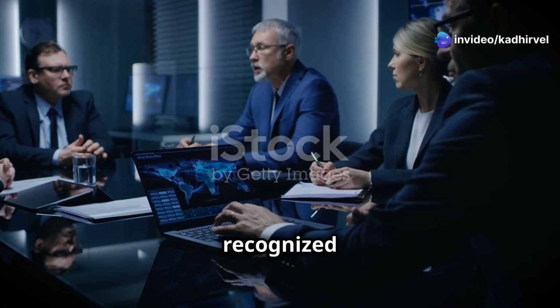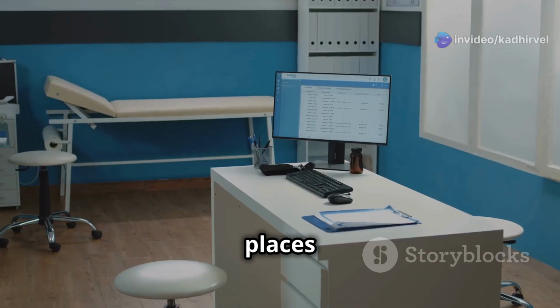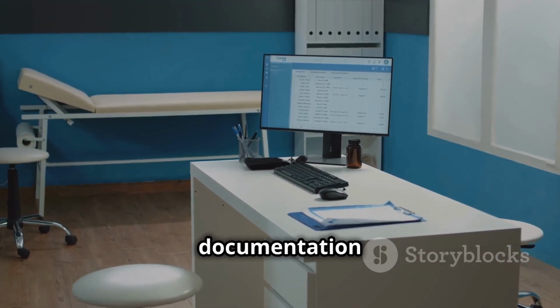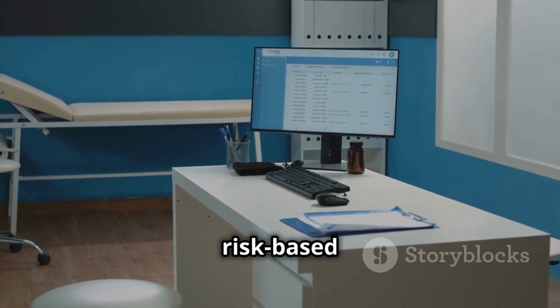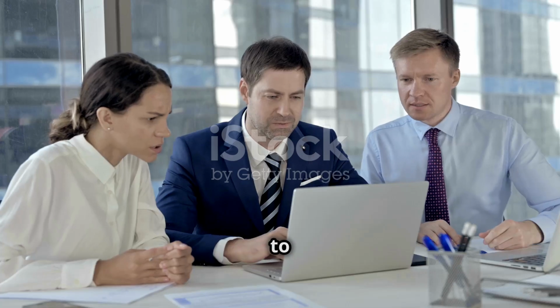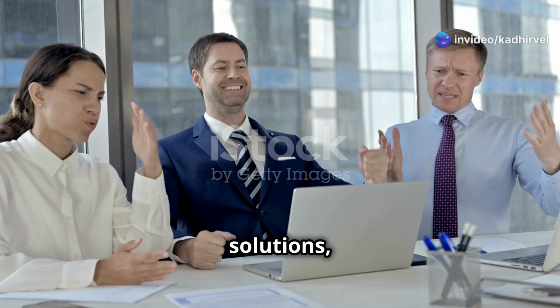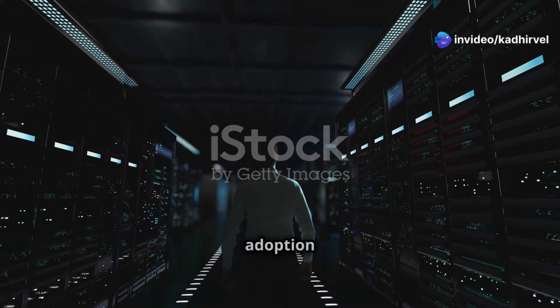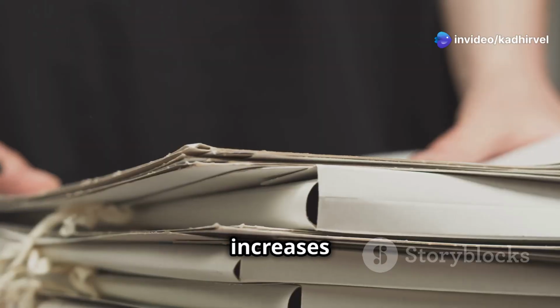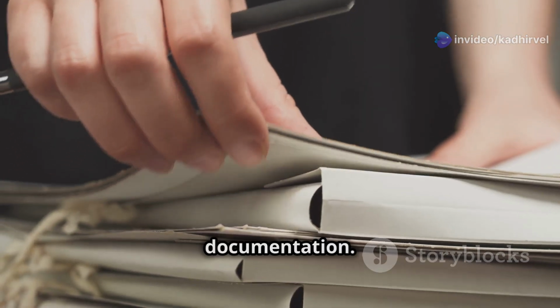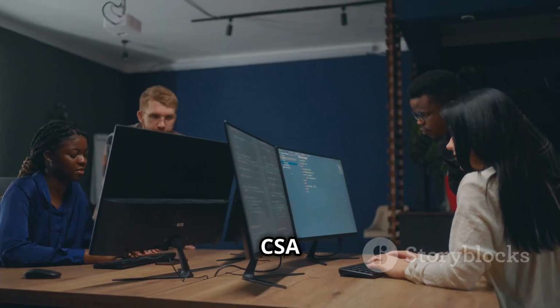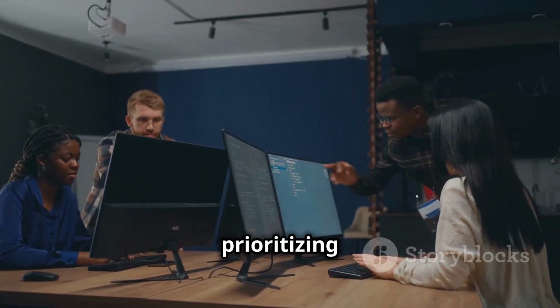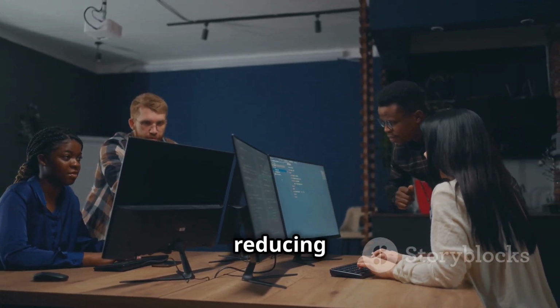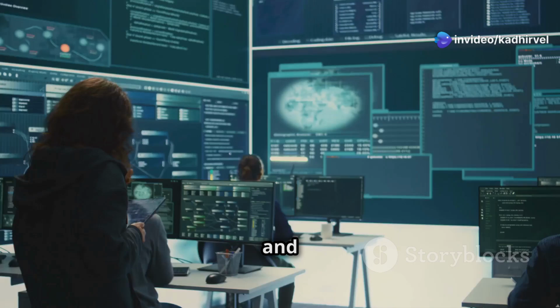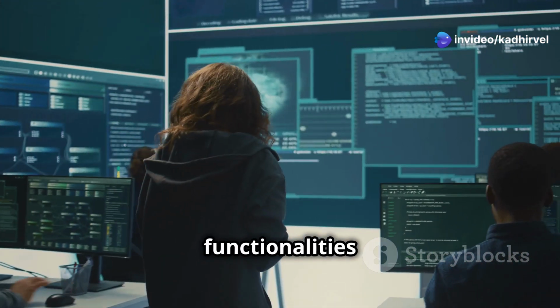The FDA recognized that traditional CSV often places too much emphasis on exhaustive documentation rather than critical risk-based testing. This leads to delays in implementing software solutions, slows innovation and the adoption of new technologies, and increases costs due to unnecessary documentation. CSA addresses these issues by prioritizing critical risks, reducing unnecessary documentation, and focusing on critical functionalities and outcomes.